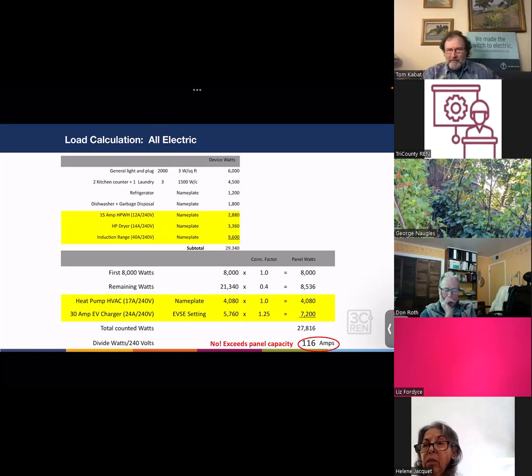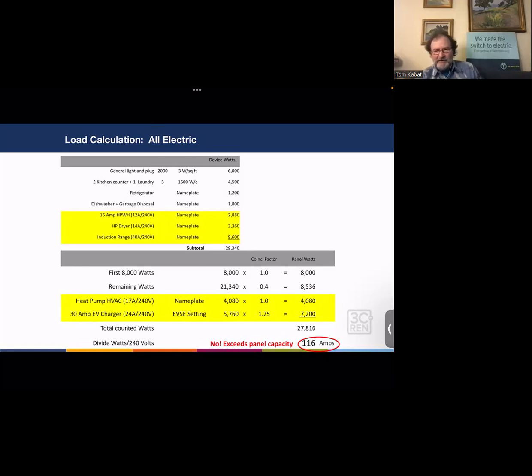Together, we total it all up, we're at almost 28,000 watts. If we divide that by 240 volts, we can tell we're over 100 amps now. We're at 116 amps. And so that one wouldn't fit on our electric panel. If we go to the next slide, we can see how it looks when you use one of the pausing devices that would monitor the whole panel and pause the EV charger if we got to that condition where the panel load went over 80% of the panel rating.